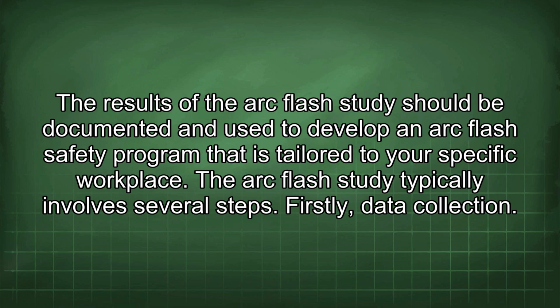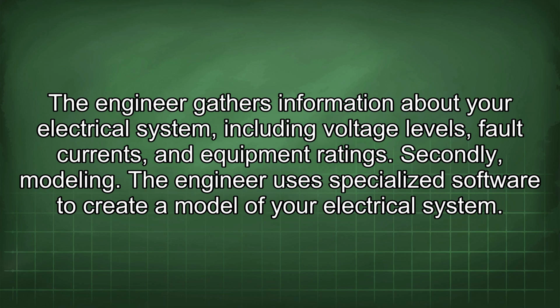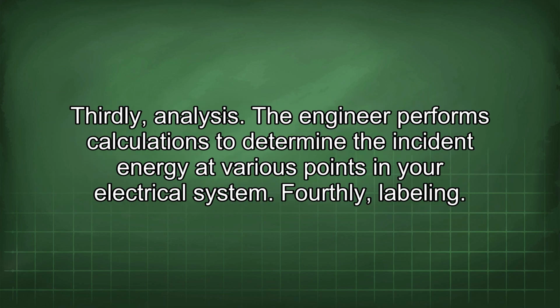The arc flash study typically involves several steps. Firstly, data collection: the engineer gathers information about your electrical system, including voltage levels, fault currents, and equipment ratings. Secondly, modeling: the engineer uses specialized software to create a model of your electrical system. Thirdly, analysis: the engineer performs calculations to determine the incident energy at various points in your electrical system.